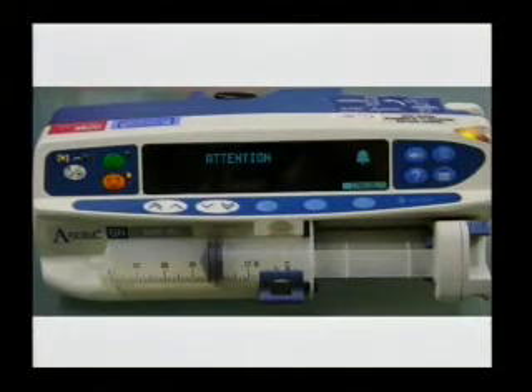Cardinal make another gadget. This is one that is used widely in our local hospitals. This is the Asena GH. And if I can point with my mouse, I just want to point out these buttons around here. This button tells you the pressure. This gives you some extra options you can get, and this purges the pump. So when you put a syringe on the front of the thing like I have here, and you connect a pipe to it, the pipe will initially have air in it. You press the purge button and it squirts stuff down the pipe until it comes out the end, and then you've got the air out of the system.